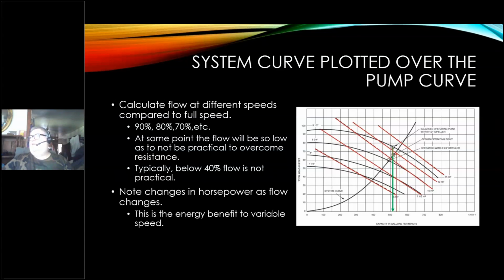If I go back the other way, though, where the horsepower crosses the system curve, I can actually get a little bit more water. That green line is where my design is. But as you can see, it intersects the system curve at a different point than the maximum on the pump curve. So we're actually operating at a different head for that line at design. So I may be able to do a little better with a lower resistance and a little bit more flow that I can tolerate.